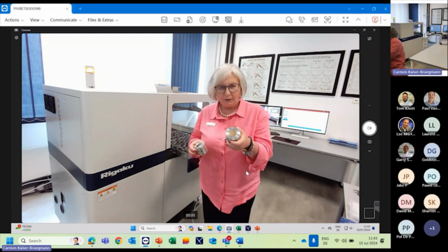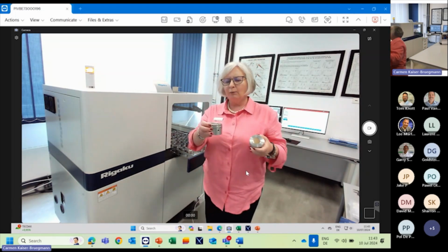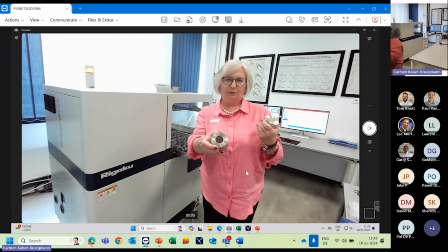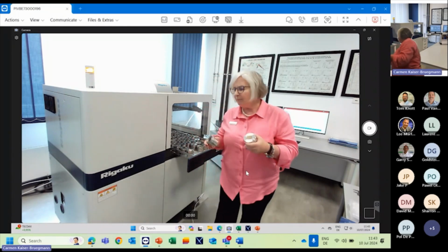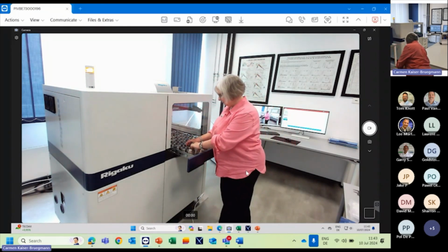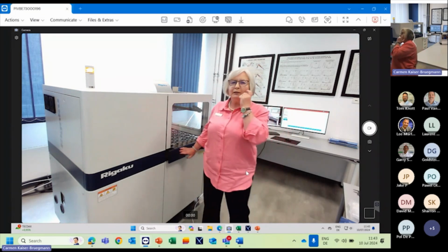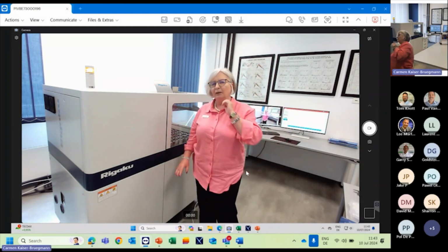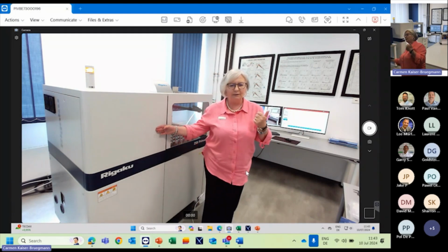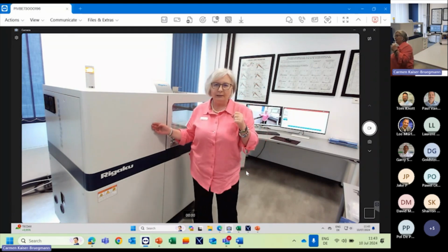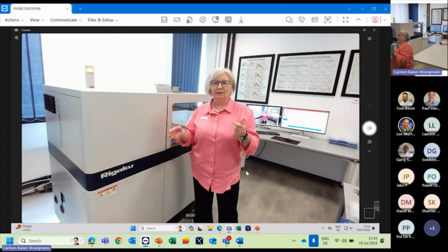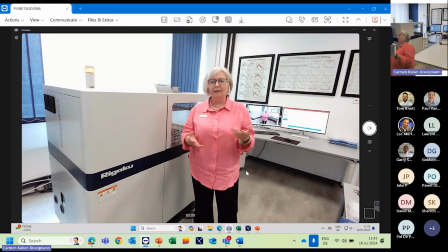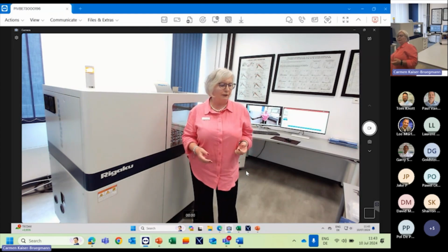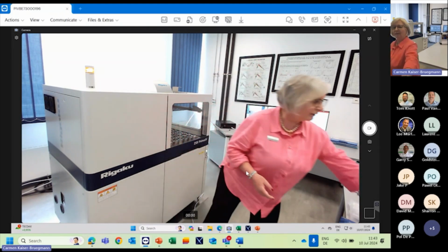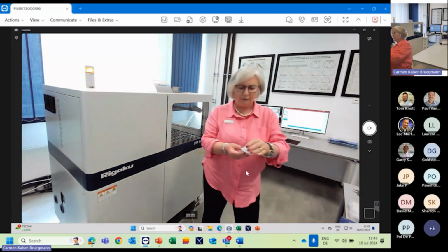We usually prepare pressed powdered samples, or we prepare fused bead samples. But there might be a situation where a customer would like to measure loose powder. And of course, the Primus 3 Next is not supplied as a helium system, so it's only a vacuum system. But that's not a problem because Rigaku has made a special cell. And the cell looks like this.